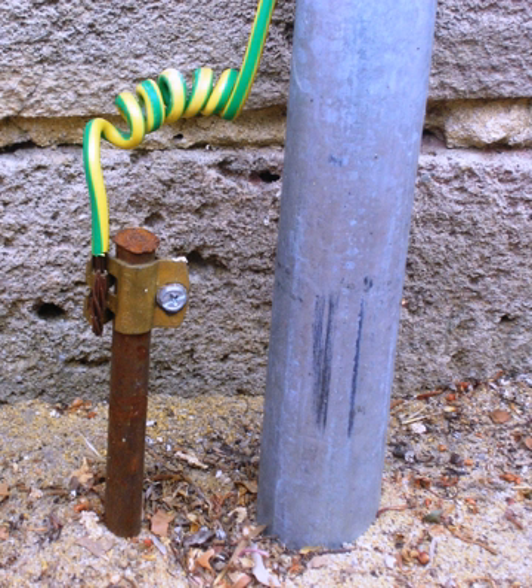Low impedance at the signal frequency of the electrode-to-earth connection determines its quality, and that quality is improved by increasing the surface area of the electrode in contact with the earth, increasing the depth to which it is driven, using several connected ground rods, increasing the moisture content of the soil, improving the conductive mineral content of the soil, and increasing the land area covered by the ground system.